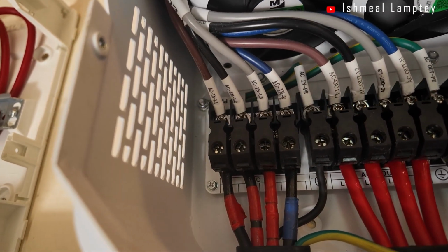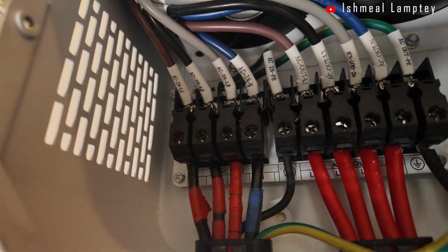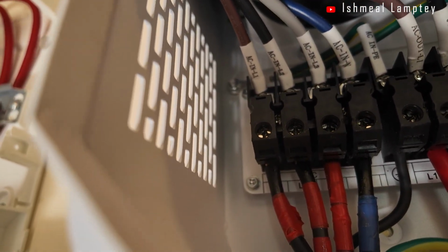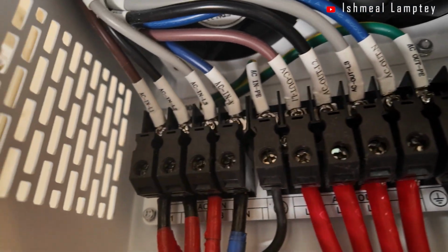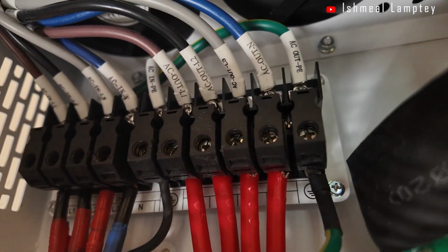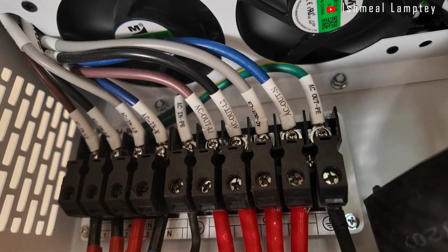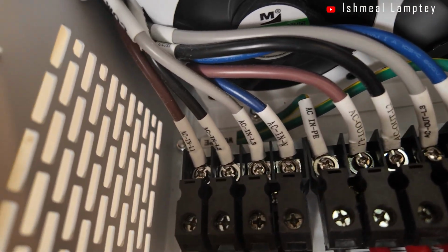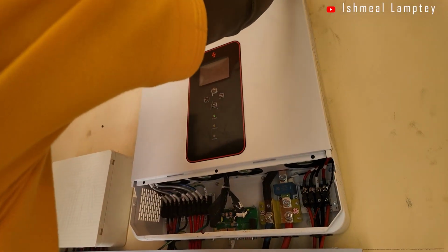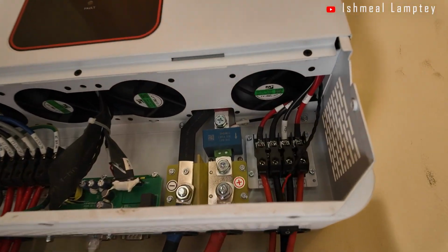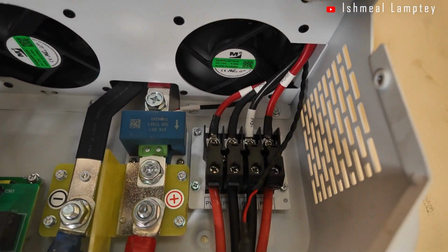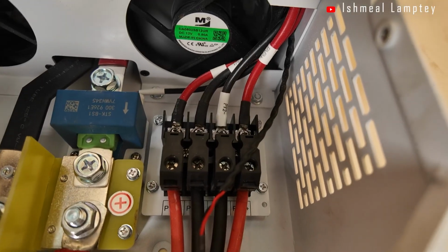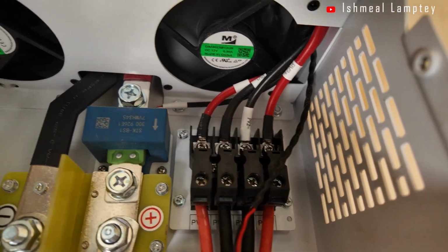And then we also had AC output. So AC output is the power generated from the solar system, which is going into the house. So we had that as well. And then we also have PV input. So the PV input is the photovoltaic system, that is the panels, which is providing power to the inverter. Now that also does two things. It does charge the battery and then also supply power to the house. So that is the configuration that we had for the inverter.